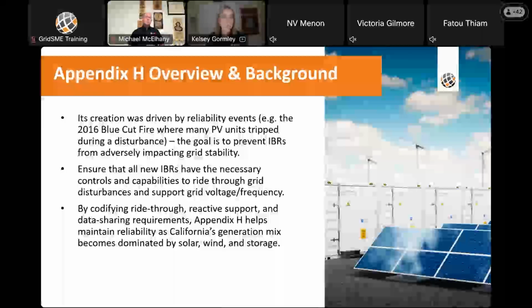So over the next few slides, I'm going to explain a little bit about each of the key requirements that are represented in Appendix H, including ride-through capacity, reactive support, talk about relevant standards such as NERC's PRC 24 for ride-through, and then also highlight how that applies to IBRs. IBRs, for the purposes of this, right now, are PV BESS hybrid projects. By the end, you'll see how Appendix H turns these resources into reliable resources that actually stabilize the grid and support grid reliability to keep our power system working smoothly.